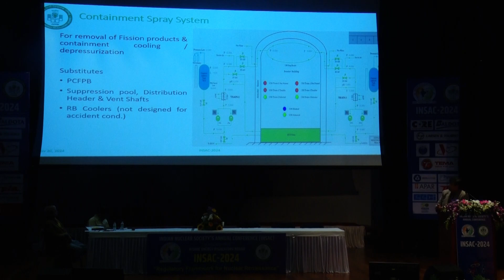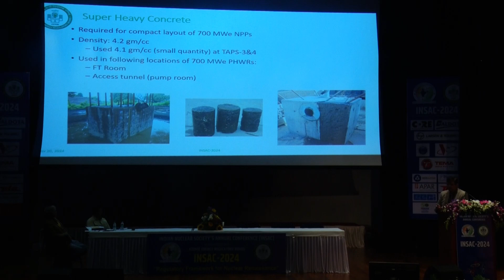Then there is a containment spray system which actually removes fission products, and it does the containment cooling and depressurization as well, and substitutes a few systems that were there in 220 and 540 megawatt PHWRs. Essentially, there are two pumps at the bottom, and then through HX it goes to the top of the containment and sprays. Then there is a super heavy concrete that was introduced for the first time in 700 megawatt PHWRs. It has a density of 4.2 gram per cc. It is used at the FT room and access tunnels.